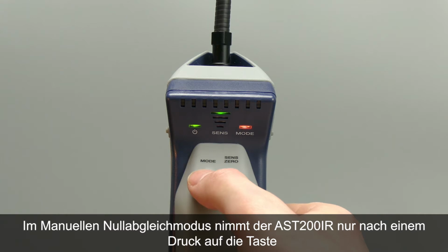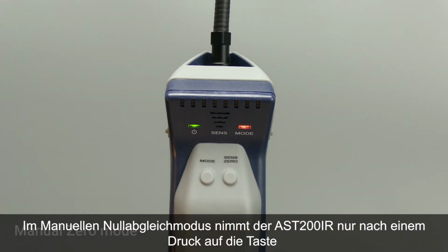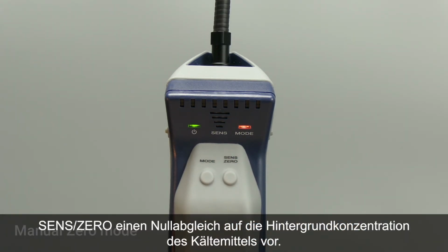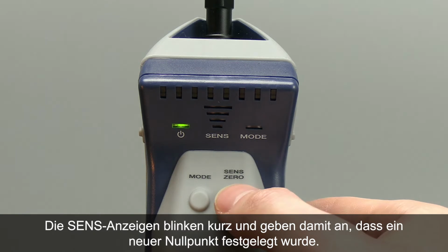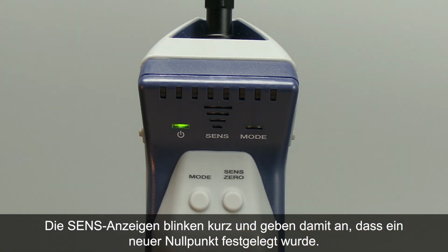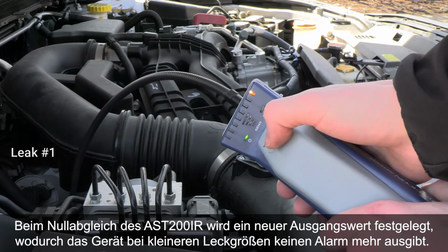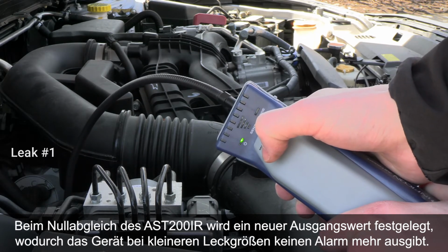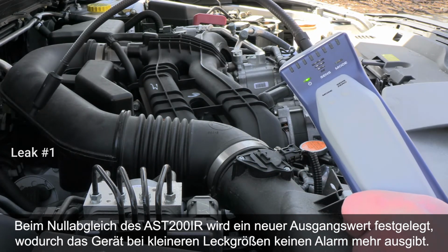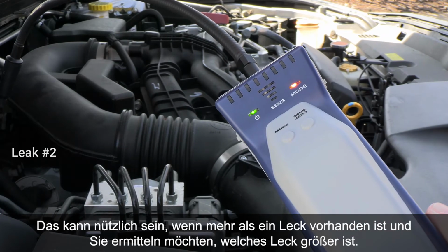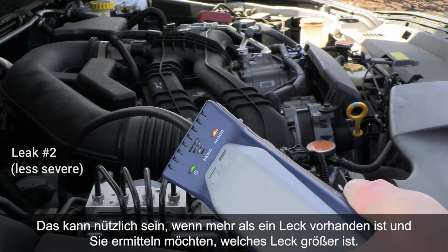In manual zero mode, AST200IR will only zero to the background refrigerant by pressing the Sense Zero button. The Sense indicators flash briefly to indicate a new zero point has been set. Zeroing sets a new baseline, so AST200IR will not alarm on a smaller leak size. This can be useful when you have more than one leak and you'd like to identify which leak is larger.